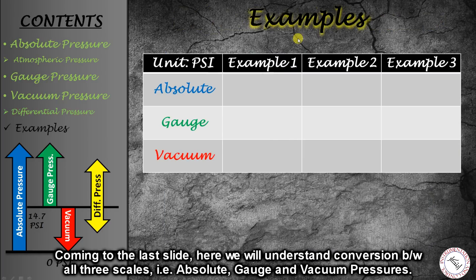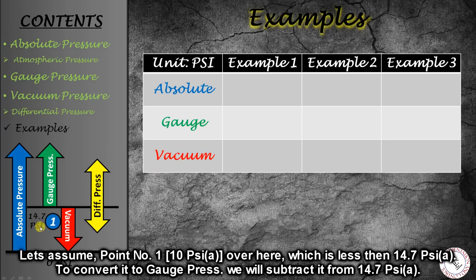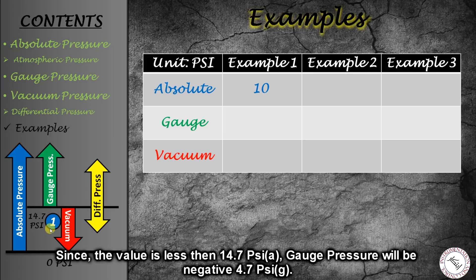Now we come to our last examples, where we practice converting between pressure scales. Point number one is below 14.7 psi absolute. If our absolute pressure is 10 psia, converting to gauge pressure: 10 minus 14.7 gives minus 4.7 psig. Converting to vacuum pressure — which is opposite to gauge — it is 14.7 minus 10, which gives positive 4.7 psiv.